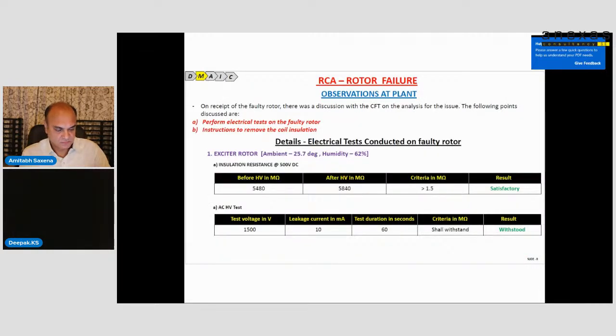Yes, we decided to do two tests. Perform two activities. One is to do the electrical test on the faulty rotor. The second thing is, based on the results of the electrical test, we decided to remove the coil insulation if required.